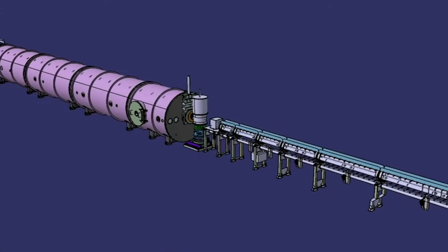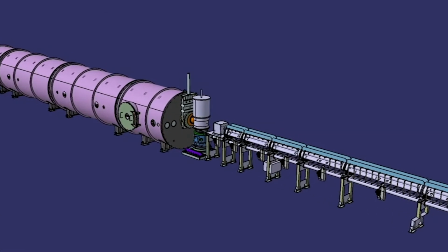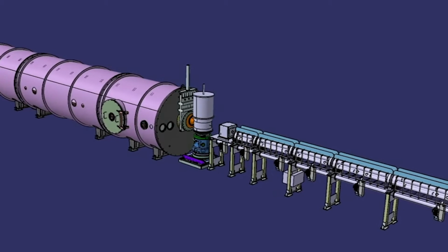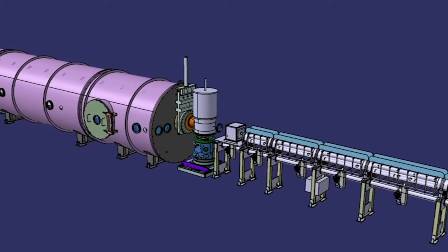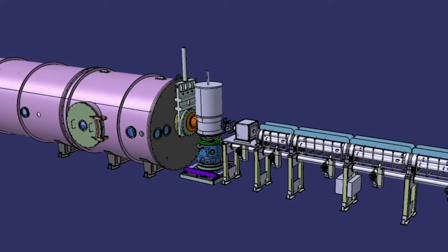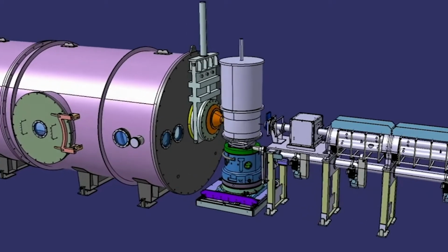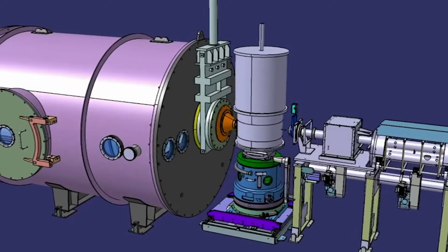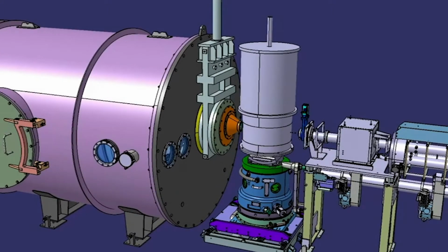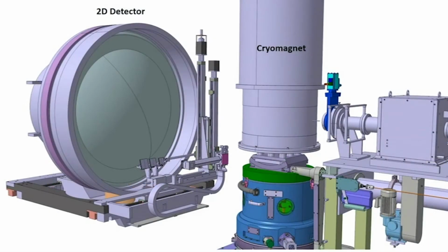We routinely perform diffraction studies of such structures using the small-angle neutron scattering instrument SANS-1. We use the instrument as a long-wavelength neutron diffractometer in a transmission geometry, where we detect the diffracted beam using a two-dimensional multi-detector placed behind the sample. Since scattering angles are just a few degrees, the use of the 2D detector allows an efficient survey of the diffracted beam, and it is often possible to measure multiple diffraction peaks simultaneously in just a single measurement.